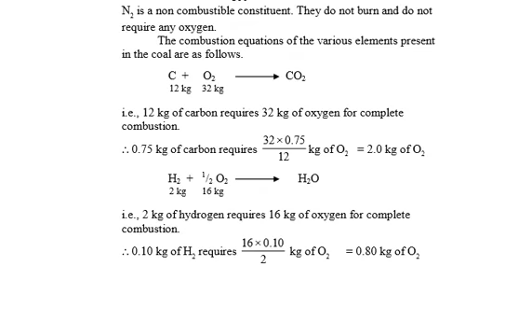Then for sulfur, 32 kg of sulfur requires 32 kg of oxygen for complete combustion. Then for 0.05 kg of sulfur, you will get 0.05 kg of O2. Then the total amount of O2 required is 2 plus 0.8 plus 0.05, you will get 2.85 kg of oxygen required for the complete combustion of the mixture. But in the given numerical, oxygen is already present in the coal, 2%, that is 0.02 kg. You have to find out the net amount of O2 required, total amount of O2 required minus O2 already present in the fuel. You will get 2.85 minus 0.02 kg, that is 2.83 kg net oxygen required.